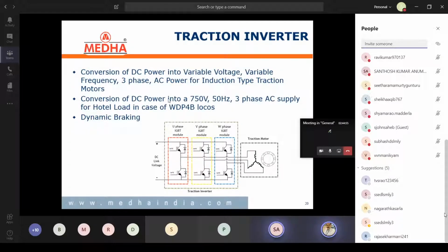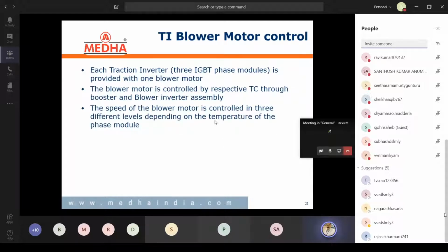So this is about the traction inverter or converter, in both directions, either in motoring or braking. Next, traction inverter blower motor control. In what we have discussed, each and every traction inverter is provided with one blower. Those blowers will run at 3 different speeds as per the temperature to get the maximum efficiency out of the IGBTs as per the OEM. Here the IGBT phase module temperature is monitored continuously, and out of 6, whichever is higher will be treated as the inverter temperature.